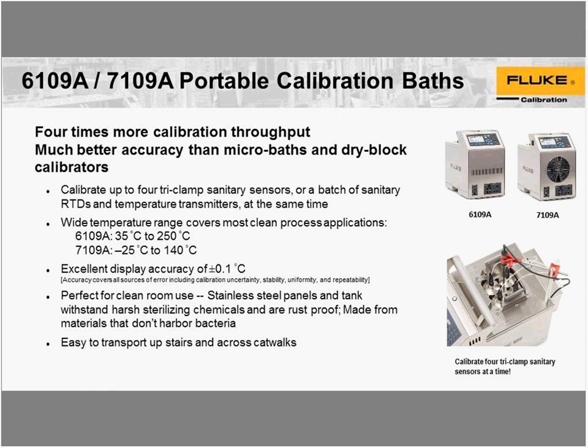or we're trying to move from using the word accuracy because it can be so confusing on what that means, and adopting terminology like maximum permissible error, even though I'm not sure that's exactly any more clear. But anyway, this, as always with a Fluke product like this, is comprehensive. This includes calibration uncertainty, or uncertainty of the reference standards used to its traceability for this instrument. It covers stability, uniformity in the tank and repeatability. So in essence, this is the measurement uncertainty. You want to look at it that way, is 0.1 degrees C.